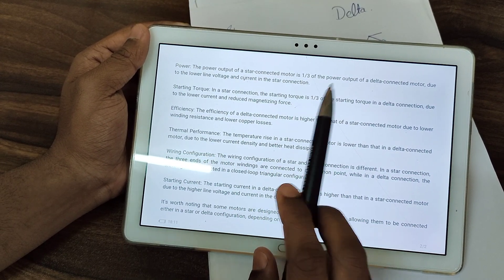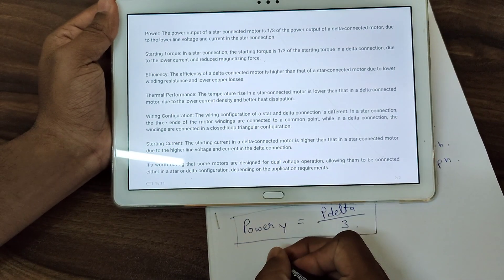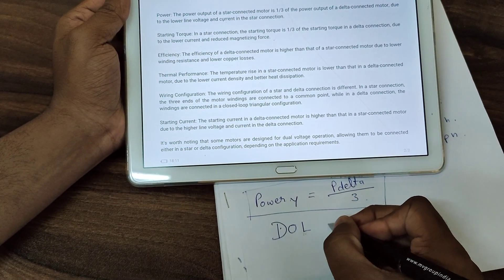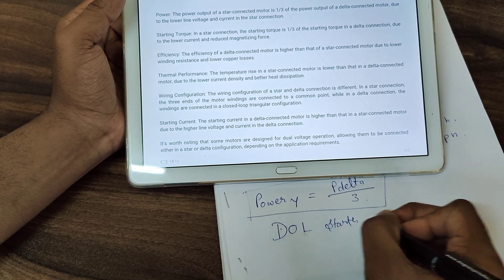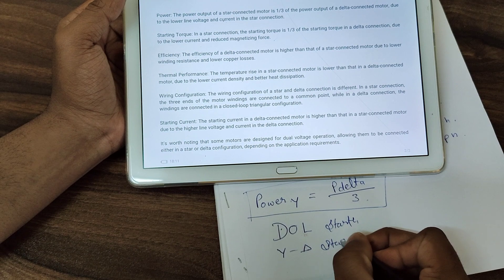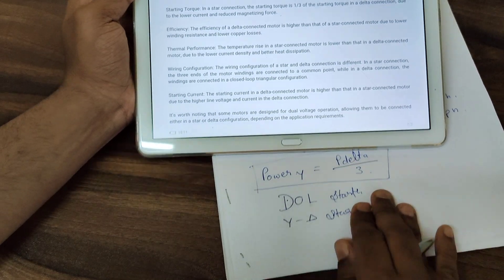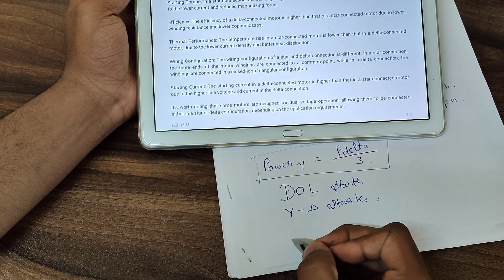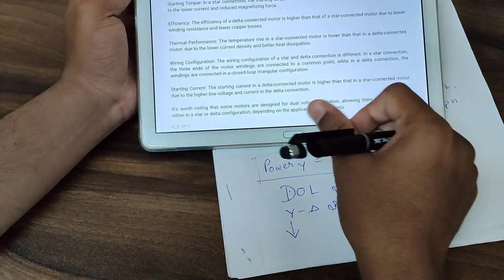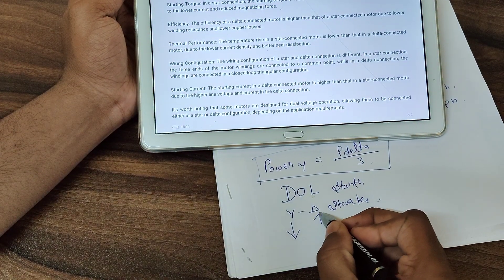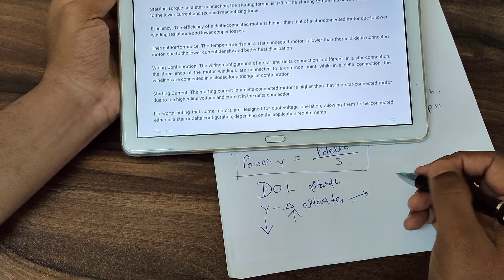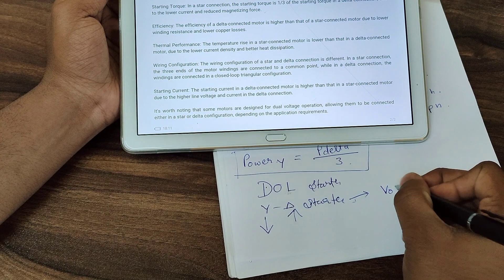In motor starting, we use a DOL starter, and after that we use a star-delta starter. The advantage of a star-delta starter is the reduction in starting current. The current is reduced in star, compared to being high in delta. This is why star-delta starters are used — to prevent voltage drops in the supply.